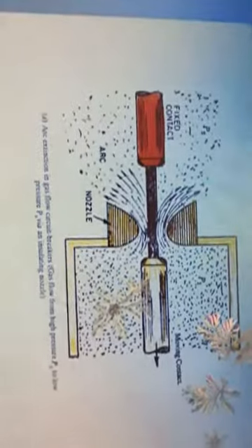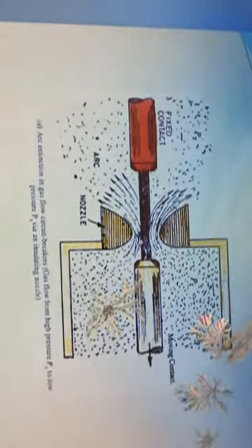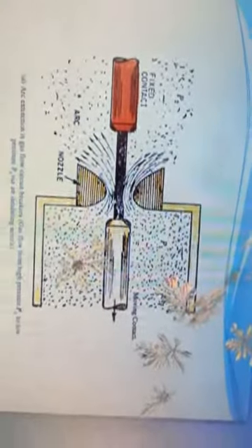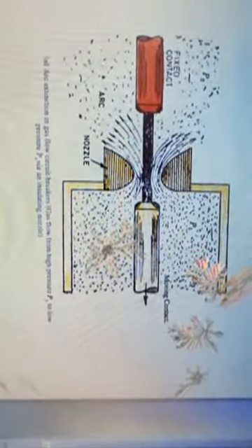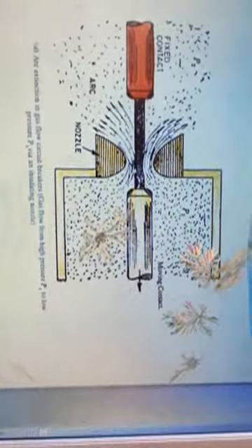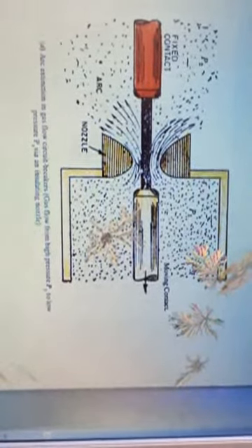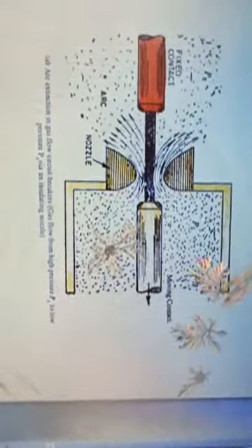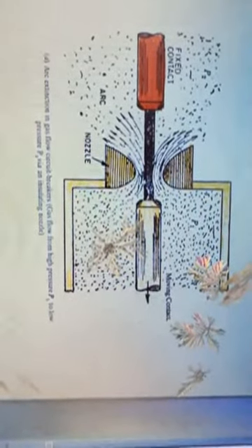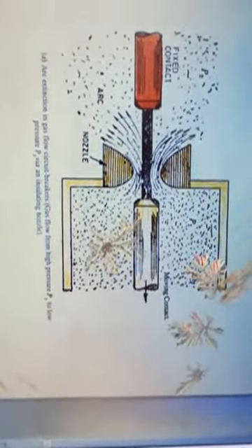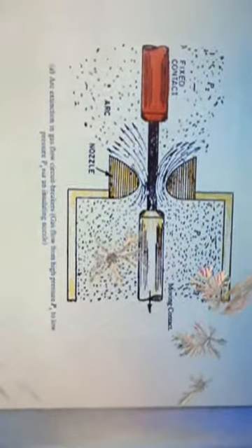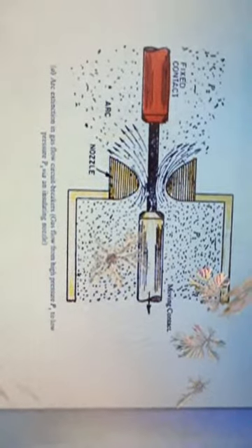Now we will discuss the chemical properties of SF6. The first is inertness. The chemical inertness of the gas is advantageous in switchgear. The life of metallic contact parts is longer in SF6 gas. Components do not get oxidized and deteriorated. Hence the maintenance requirement is reduced.